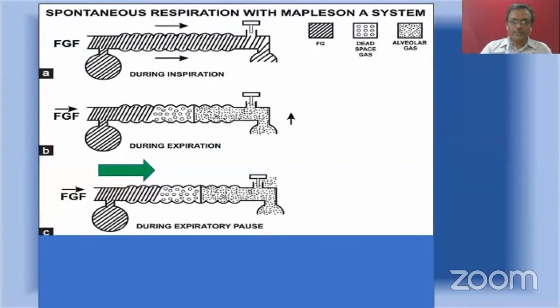Now we reach the expiratory pause. During expiratory pause, there is no flow from the patient because it is a pause. So in expiratory pause, there is no respiratory movement. The only flow happening in this circuit is the fresh gas flow. So what will happen? The fresh gas flow will push the alveolar gas and dead space gas towards the APL valve, and you can see clearly that the valve is opening, because 1 centimeter of water pressure is sufficient to open up the valve, because you have kept the valve in an open position, isn't it? Now the alveolar gas is going out, and the expired gas, which contained carbon dioxide, has gone out.